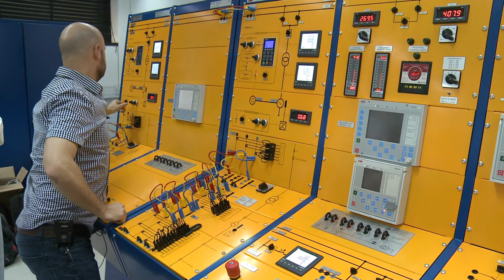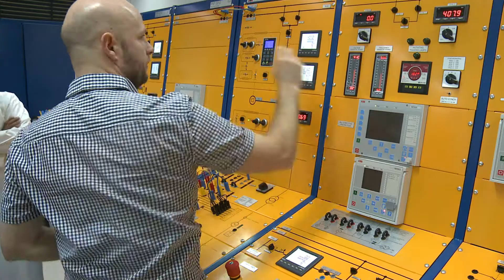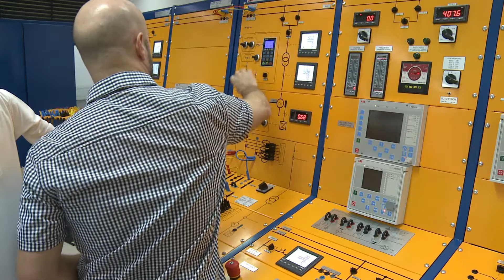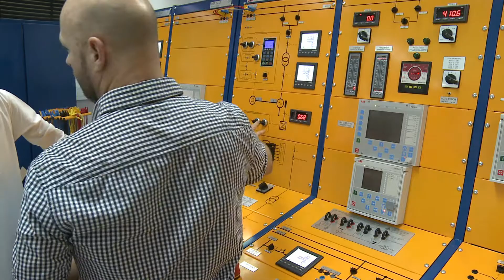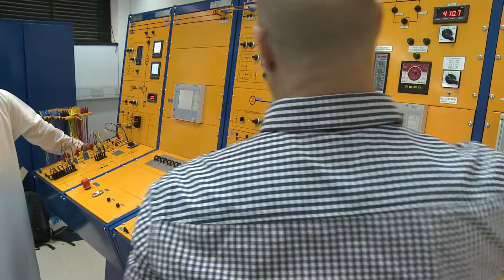Switching off this one. So now I have no grid and only one generator. Yes. Just now we have both of these in manual position. Yeah. Okay. So with both of these in manual, or even if I put the motor into auto, I can do that. We should hold our speed when we start to load, but the voltage will probably drop. Hopefully the frequency won't drop because we have auto. We have some feedback in this one, and it should hold that position. So we try that one first.